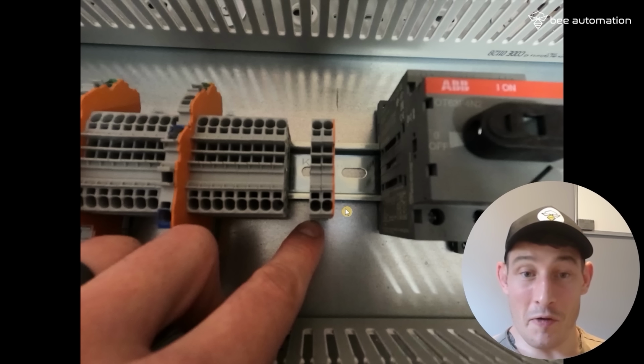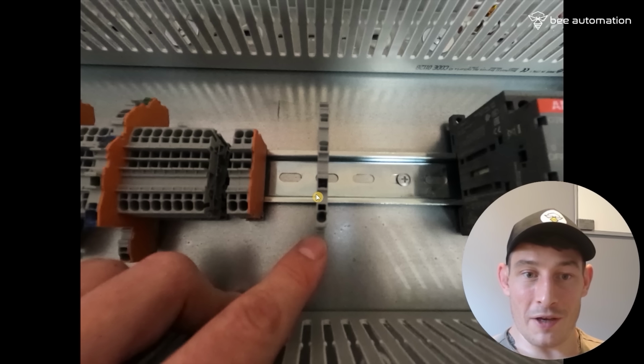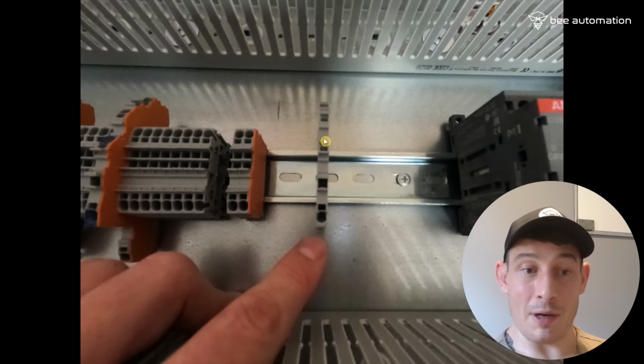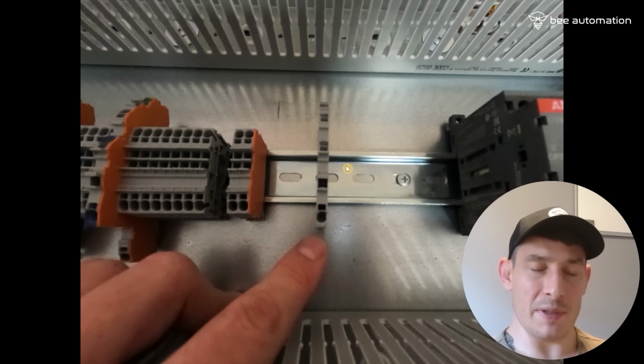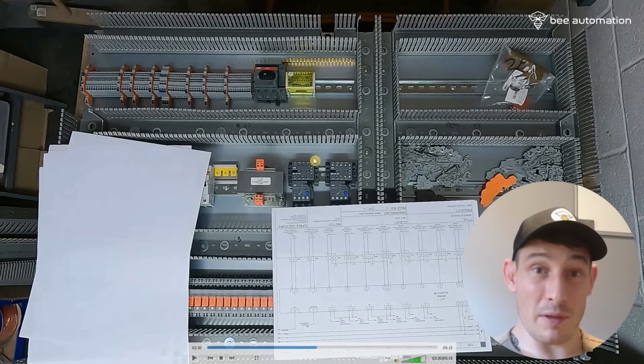But the beauty of Wago, rather than using two single terminal blocks, we can use one double terminal block. That's going to save space and let us move the main isolator over to the position we need, so you'll see me work through that in a second.